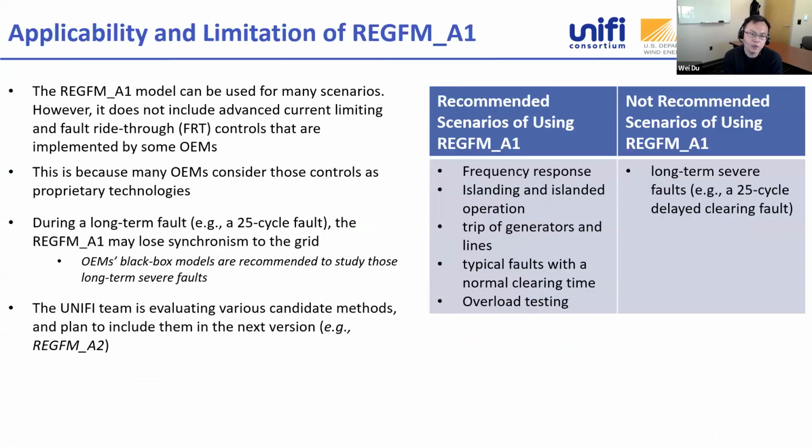And here I'd like to summarize the applicability and the limitations of this model. I think this model is quite good for studying many typical events like frequency response, islanding and islanding operation, trip of generators and trip of lines, typical faults with normal clearing time, and even overload testing.